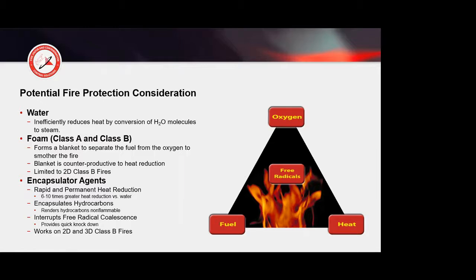They blanket and separate the fuels from the oxygen to smother the fire. To us, a counterproductive thing of the foam is we're putting down a blanket. And I know that when I'm lying in bed at night and I'm cold, what do I do? I pull up a blanket because it insulates me and traps in the heat. And that's exactly what we see with the foam. So you put a blanket down, it's going to trap in that heat.